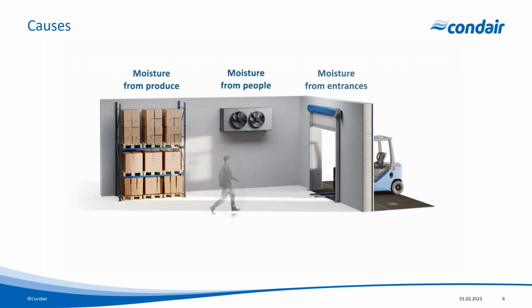Moisture from entrances is really the biggest form of moisture that's going to come into the space. And this is really where we've got an entrance. We've got two different temperatures, both inside and outside the cold store. Well, we've got two different temperatures and two different humidities. We get an imbalance in vapor pressure. And vapor pressure will always try and equal out. It will always try and go from the high to the low. So when we have that difference in vapor pressure between the outside and inside, moisture will be forced into the cold store from that doorway.